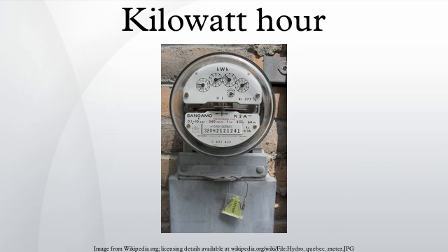Examples: a heater rated at 1000 watts, operating for 1 hour, uses 1 kilowatt-hour of energy. A 40-watt light bulb operating for 25 hours uses 1 kilowatt-hour. Electrical energy is sold in kilowatt-hours. Cost of running equipment is the product of power in kilowatts multiplied by running time in hours and price per kilowatt-hour. The unit price of electricity may depend upon the rate of consumption and the time of day. Industrial users may also have extra charges according to their peak usage and the power factor.